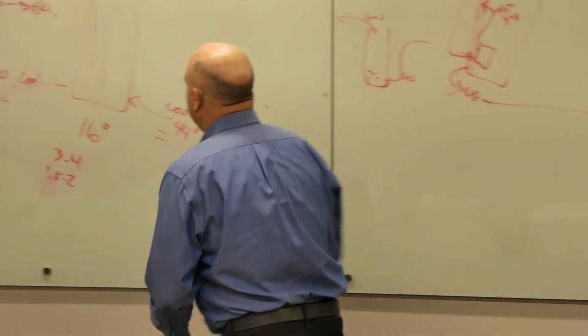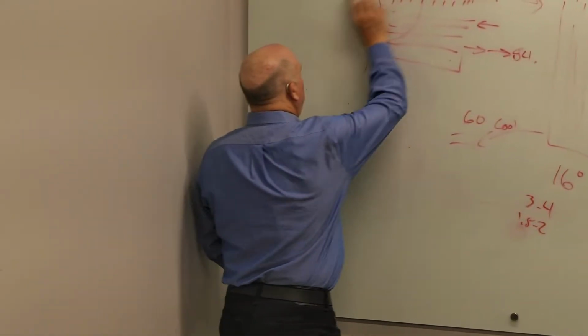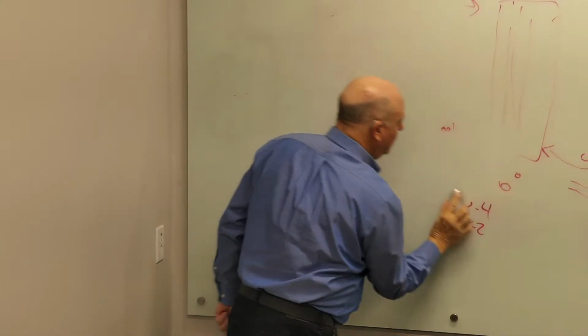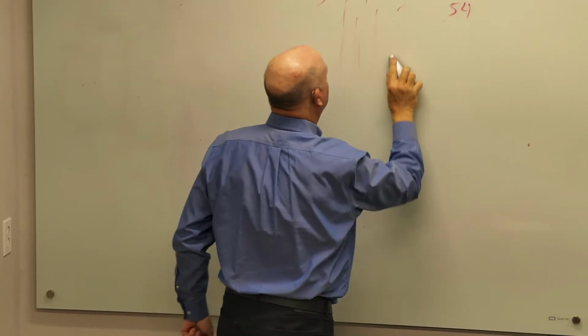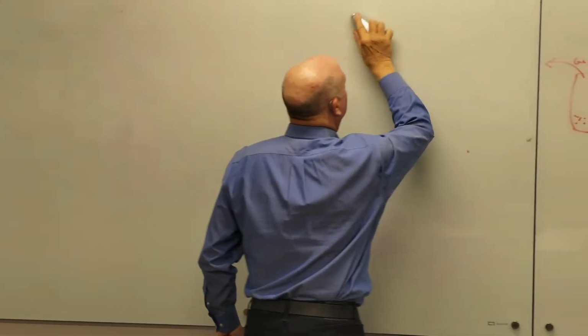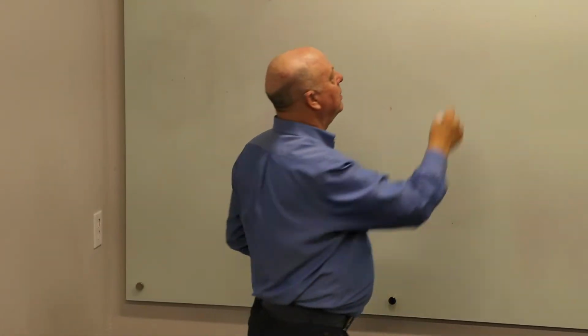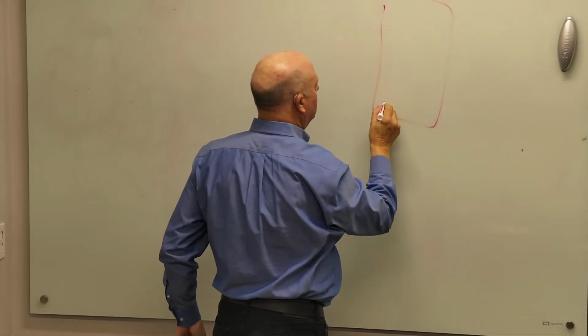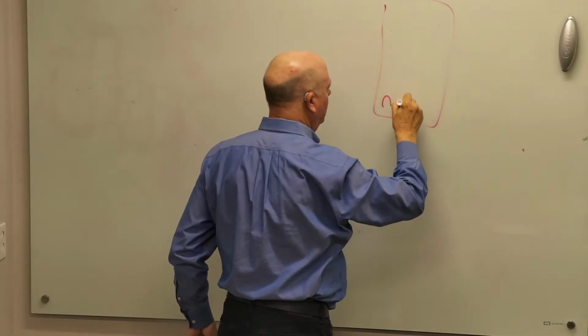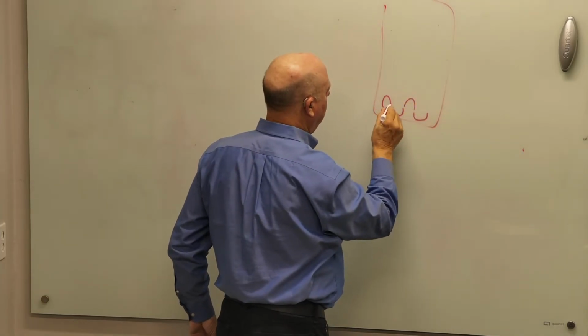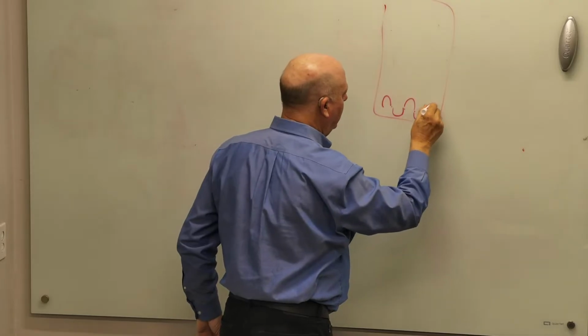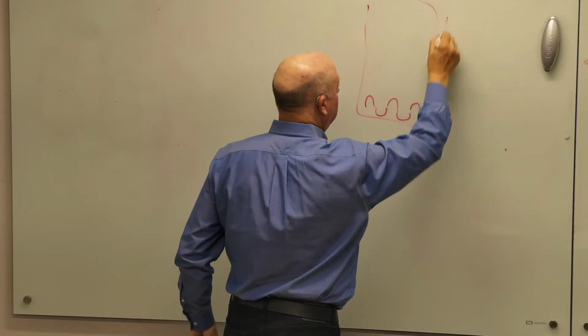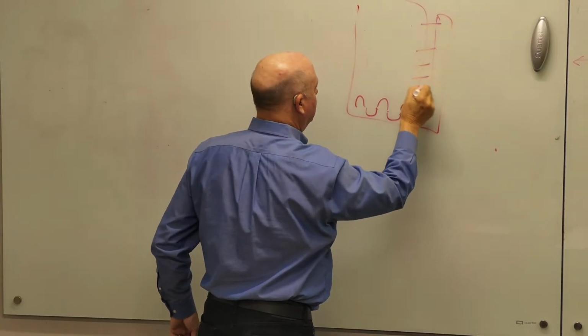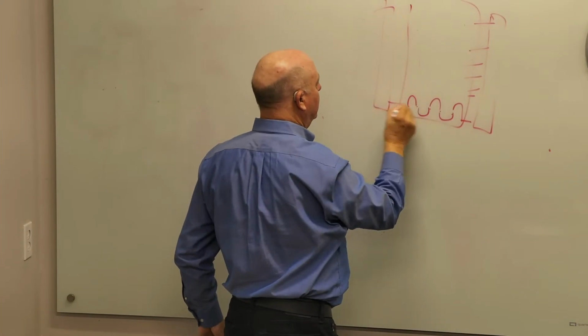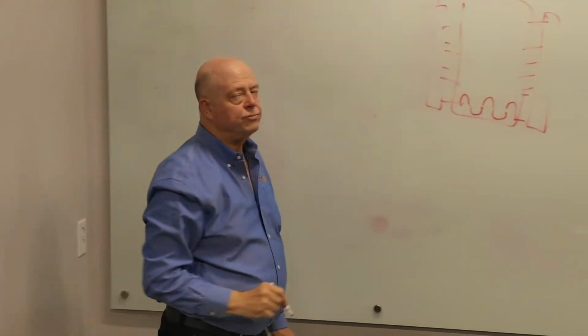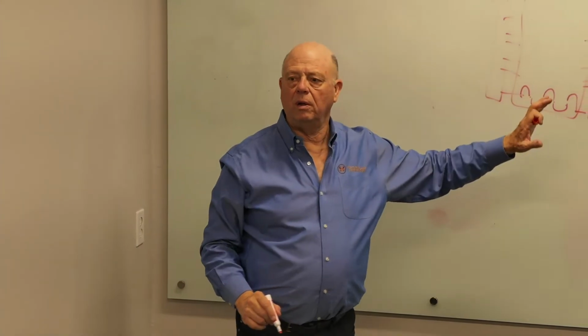The one point I wanted to get to with all this is, if you've got a coil, you have to pipe so that you get the counterflow and not the parallel flow. So let's say this is a cooling coil, and it's 6 rows. I get to the other side, I come around, and around, 1, 2, 3, 4, 5, come around. And then I go to a header. So I got a header with all these connections, and I got another header with all these connections. 6 passes for a 6 row coil.